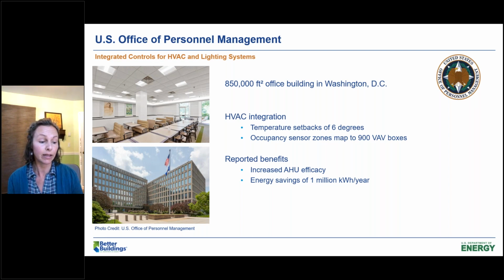The site upgraded their lighting system, ensuring all luminaires in non-storage and mechanical spaces were dimmable and addressable. They set back temperatures in unoccupied spaces by 6 degrees, and they mapped their occupancy sensor zones to 900 separate VAV boxes. Their efforts not only increase the air handling unit efficiency and longevity, but also save them 1 million kilowatt hours per year.